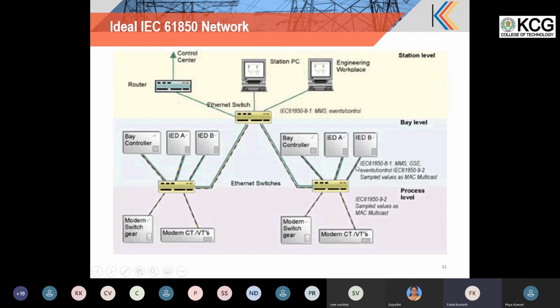All are connected via Ethernet, and even the station level equipment like a station PC, engineering workstation, HMI, alarms, everything is connected on the Ethernet. So this is the ideal 61850 network. All the buses are connected over the Ethernet and communicate.